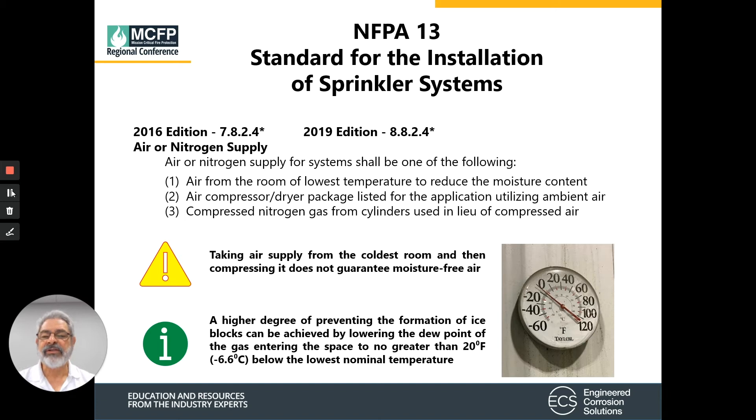NFPA 13 tells us that our supply of gas has to be one of three options: if it's air, it must come from the lowest temperature room to reduce moisture content; it can come from a compressor dryer package listed for the application; or the third option is compressed nitrogen gas from cylinders in lieu of compressed air. The best thing we can do is ensure that the gas is at least 20 degrees below the lowest nominal temperature.